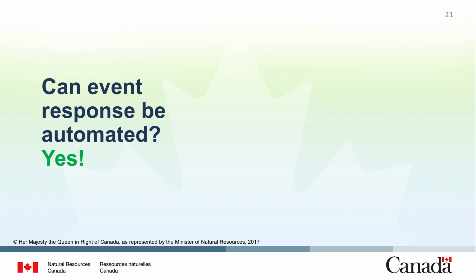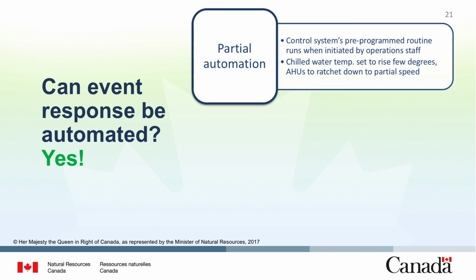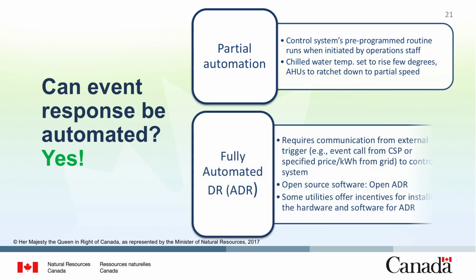To facilitate participation in demand response programs or site-level demand management, some of the functions can be automated. Partial automation generally involves using the building's energy management system to have pre-programmed routines run when initiated by operations staff or on predetermined demand thresholds. For instance, chilled water temperature can be set to rise a few degrees, and air handling units can be ratcheted down to partial speed. Fully automated DR, known as ADR, requires communication from an external trigger, such as an event call from curtailment service providers or a specified price per kilowatt-hour from the grid, to control systems.